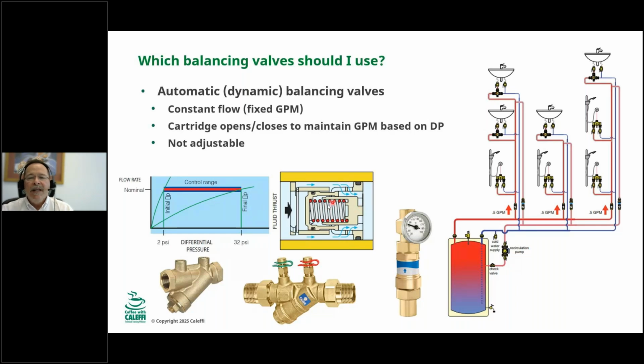And it's designed such that that characteristic opening and the compression of the spring match up so that you get a constant GPM between a given differential pressure range. Like from 2 psi to 32 psi, this valve would stay at a constant GPM. So what you do is you order these based on that GPM. You could order a valve with a 1 GPM spring or a 2 GPM or 1.5 or 6 GPM. And what that means is the size of these openings right here will vary based on the GPM you want. So it's all calibrated to work together.